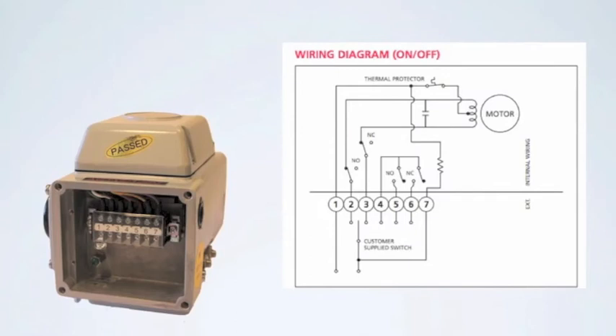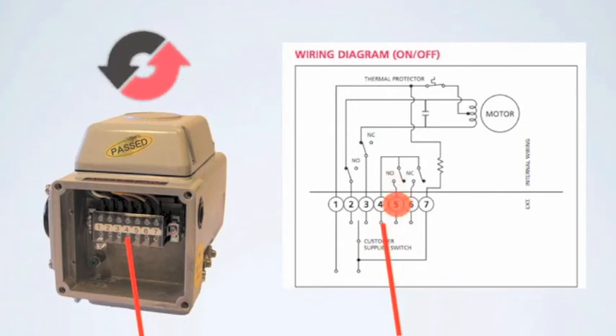Dry contact limit switches are available for control room feedback. Apply common power to Terminal 4. When the actuator reaches the full open position, switch contact is made and feedback is available on Terminal 5. When the actuator reaches the full closed position, switch contact is made and feedback is available on Terminal 6.